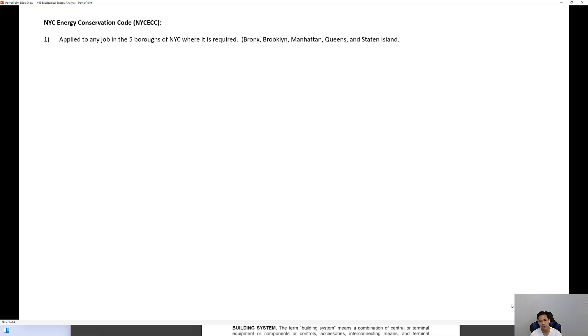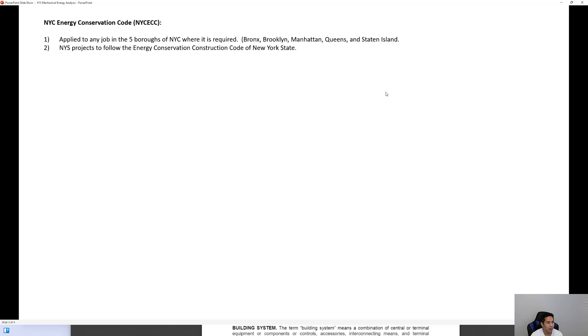The NYC energy code is applied to any job in the five boroughs of New York City — the Bronx, Brooklyn, Manhattan, Queens, and Staten Island. For projects outside the five boroughs but within New York State, you follow the Energy Conservation Construction Code of New York State. Projects in New Jersey follow the International Energy Conservation Code, abbreviated IECC.